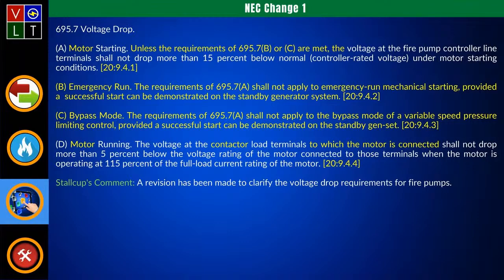And then I showed how to calculate it using two different methods. I showed how to do it using 2 times R times L times I divided by 1,000. And then we also did it based on circular mils, using chapter 9, table 8. We went through that, and then we even found out which one would carry more, which would have less loss, between a solid and a stranded conductor. That was a good one. That was extra information I pulled out for that one.